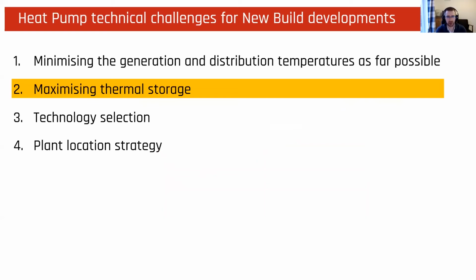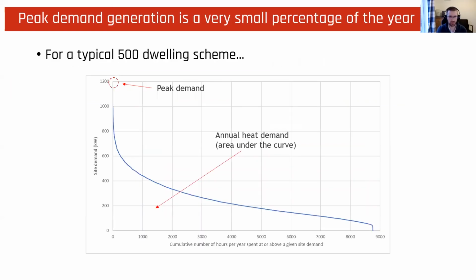So the next thing I'm talking about is maximizing thermal storage. The reason thermal storage is so important for optimizing heat pump design is because of the nature of residential heating and hot water demand being extremely peaky. So we have really short duration but large demands that represent the peak demand when we have a coincidental coldest day outside in the morning when people want hot water. We have a surge in demand, but for most of the year the demand is actually, it's like a base load. It's very, very low level demand, which kind of divorces what we want the heat pump to be doing for our base load generation from our peak demand situation.